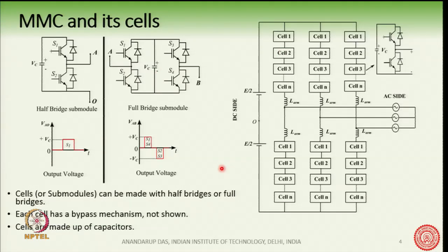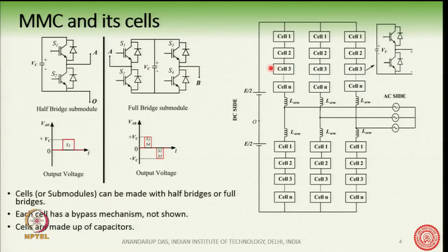Inside cell 1, cell 2, cell 3, and so on, either the half-bridge or the full-bridge is used. When to use each variety we will understand a few slides later. Taking the simpler case — the half-bridge — each cell is made up of half-bridges. There can be n number of cells, and n can be more than 100 for high-voltage DC transmission at ±400 kV.